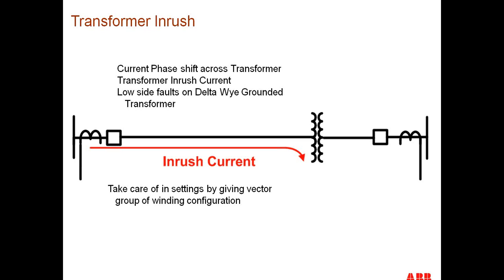But remember, back when we talked about communications and transmitting information across the line, we also mentioned that you can transmit sample data across the line. And because we're transmitting sample data across the line, we can calculate at each terminal what the harmonic components are. And just as we do in transformer differential protection, we can put a harmonic restraint element in the line differential relay and set it so that it can detect this inrush current and block the relay from operating during this inrush current condition. So that's fairly easy.